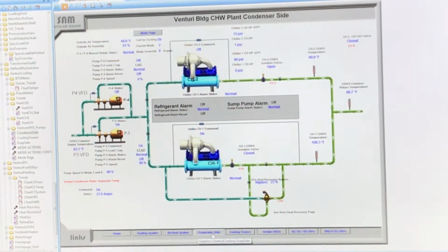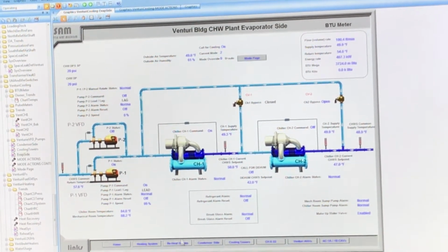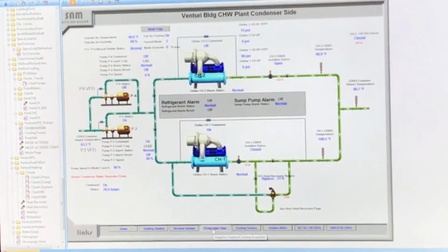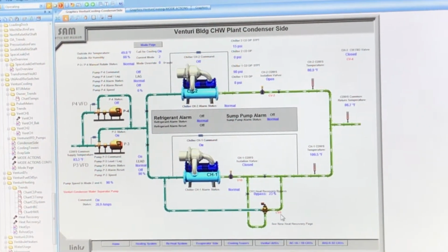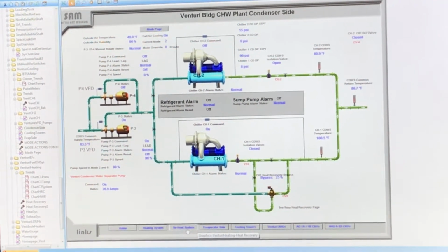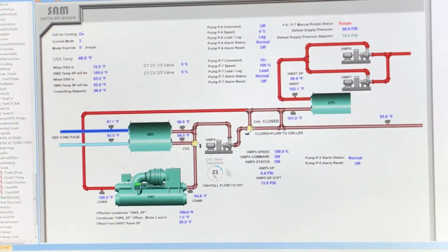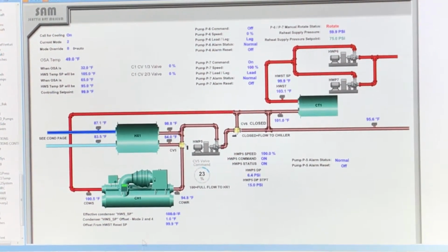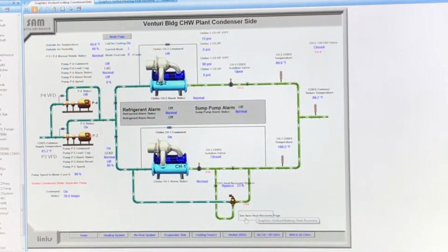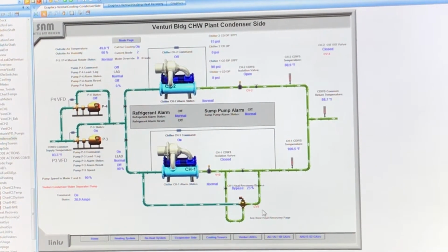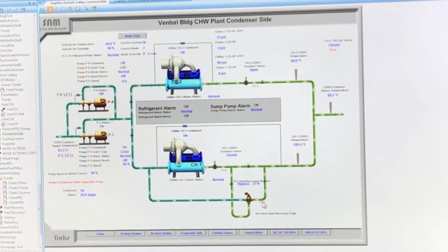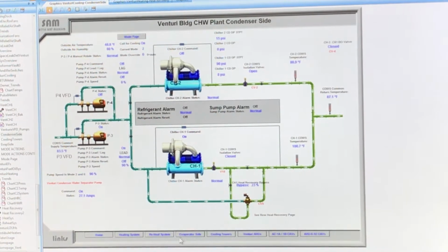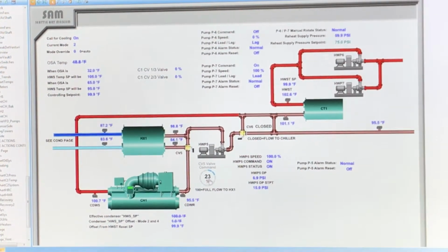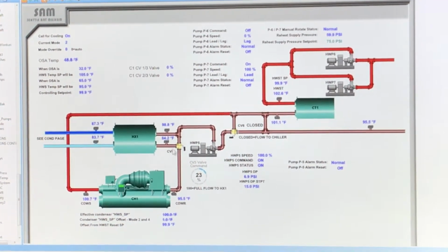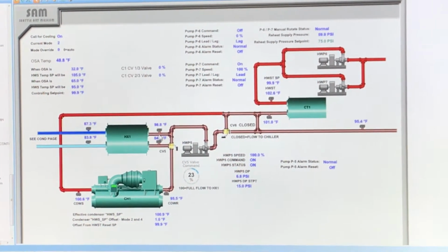Okay. We did the evaporator side, right? Can you go back to that other page real quick? Now, the CV5 down there is also on the same graphic as the reheat loop, so it's not actually a bypass technically anymore. Right here it says see new heat recovery page. The CV5 is now modulating to create heat for you, as a control valve to dictate the temperature coming out of the condenser water. So the condenser water comes out and the CV5 modulates it through the heat exchanger.